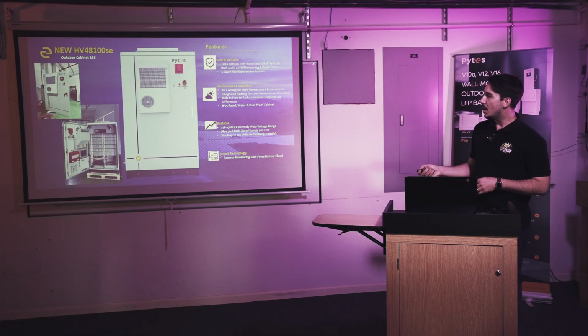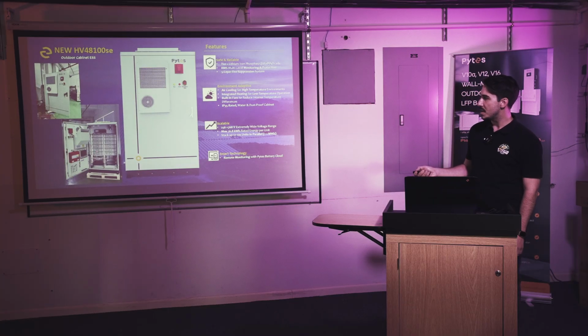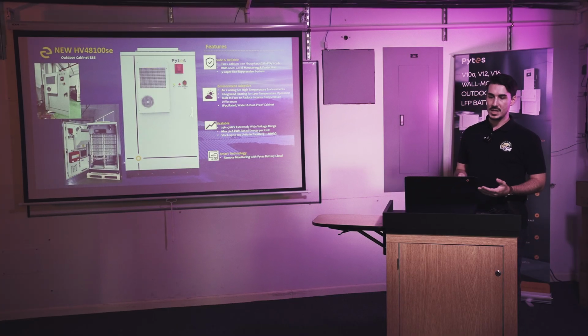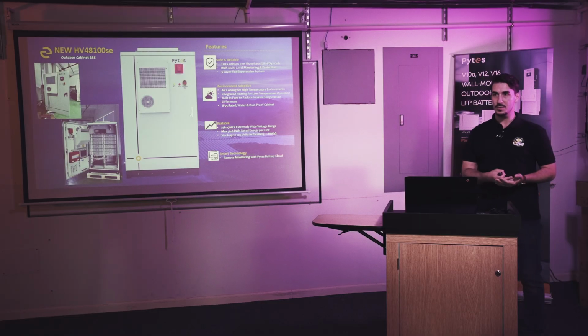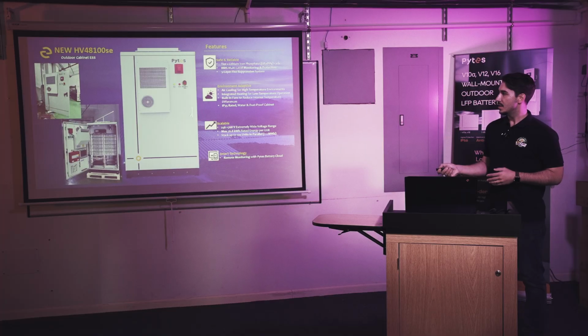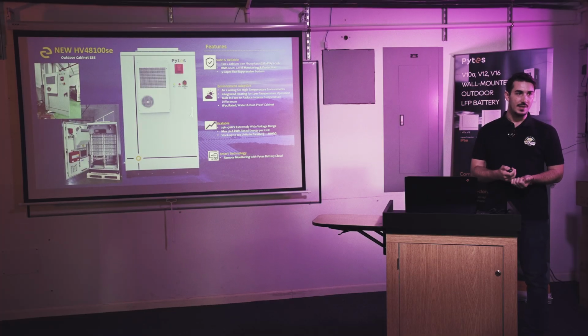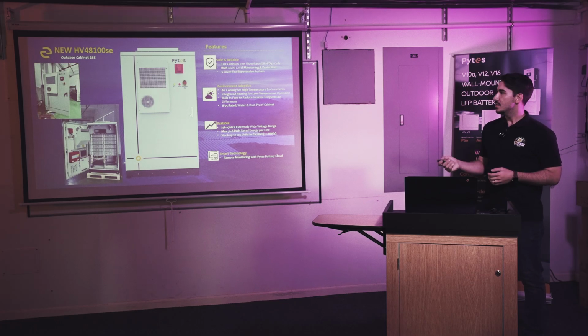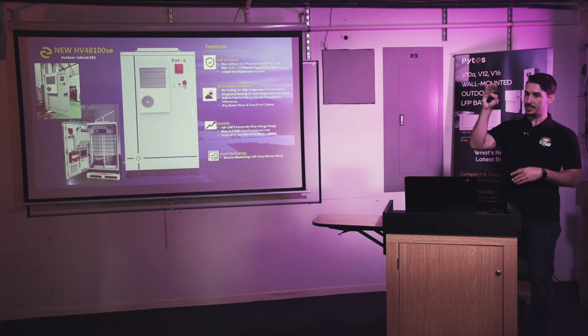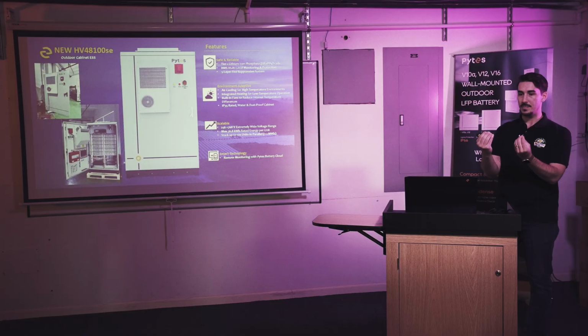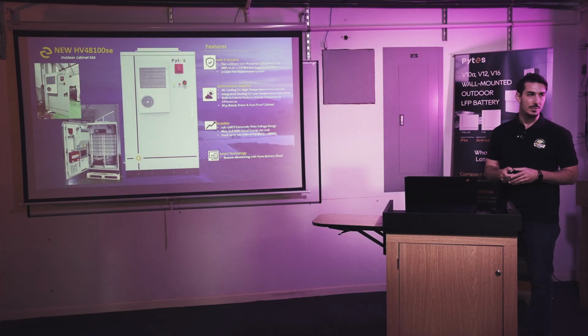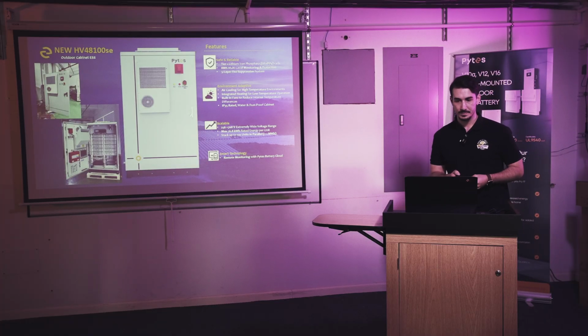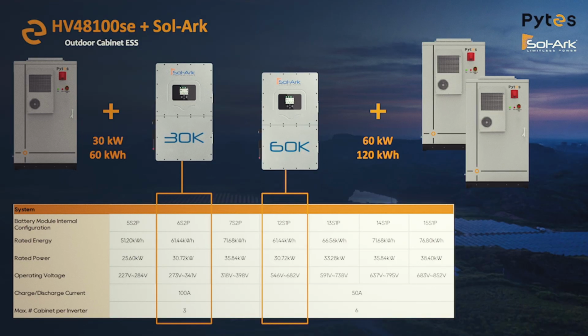And then the other thing is the modules have been completely redesigned. It's maybe kind of hard to see, but the battery modules are still the same 5 kilowatt hours, 51.2 volt nominal batteries. They're connected in series, but the modules now have built-in heating pads, and they also have built-in ventilation fans. So we've got a heat pump on the outside of the cabinet that's going to do heating and cooling, and that blows the conditioned air towards the back of the cabinet, and those fans built into the modules individually pull that air through the battery to even further regulate temperature. And as I said, those modules have heating pads too. So a lot of the configuration we looked at with the indoor cabinet still applies to the outdoor cabinet.